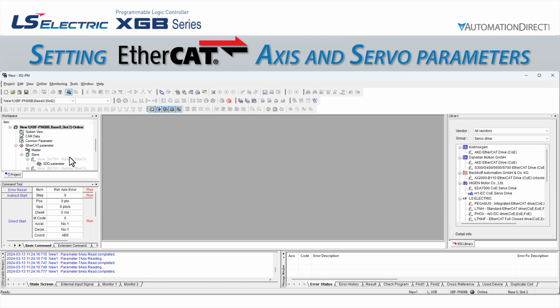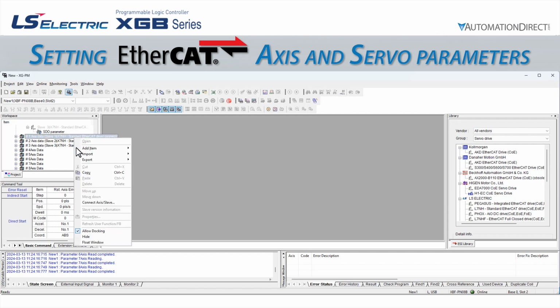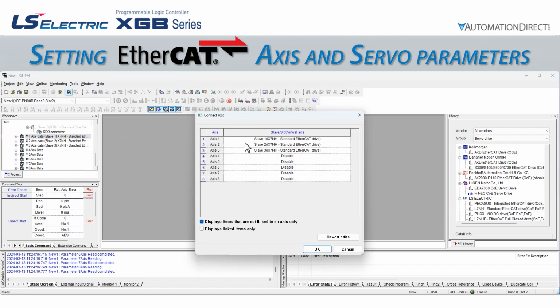Once we have our EtherCAT network physically connected and our drive nodes identified and assigned to axes, we are ready to configure the parameters for those axes, as well as the servos themselves. The axis parameters are contained in the XGPM software, and if we were to remap which axis went with which drive, those parameters would stay with the axis number.